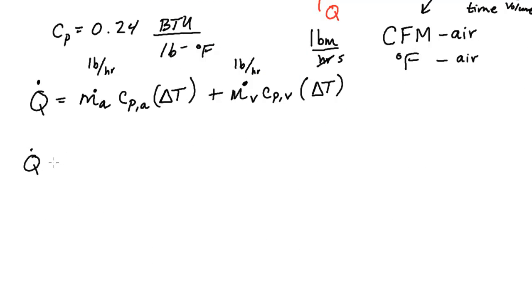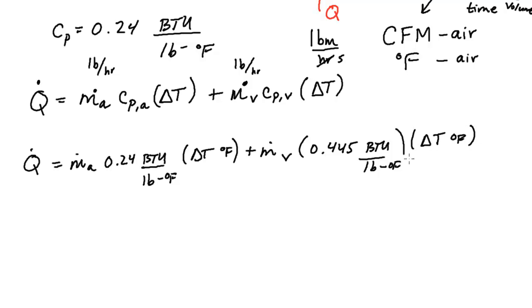So let's do some filling in. We have Q is equal to the mass flow rate of air. We now know that this term is 0.24 BTUs per pound degree F multiplied by a delta T. That's also in degrees F, plus the mass flow rate of vapor, times 0.445 BTU. So again, water vapor. Water has a much higher specific heat than just air by itself, which again is nitrogen, oxygen, and items like this, also multiplied by our delta T in degrees F.